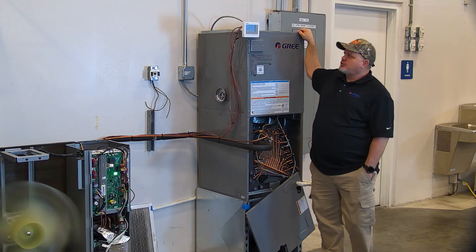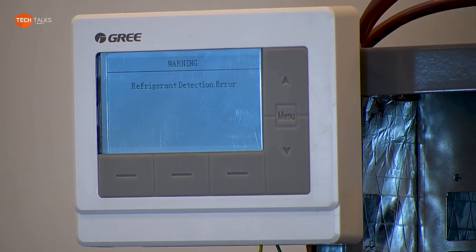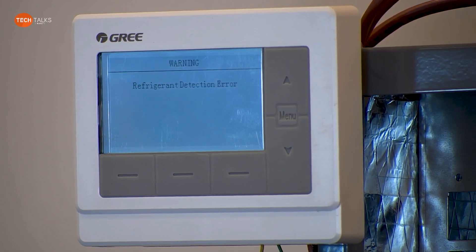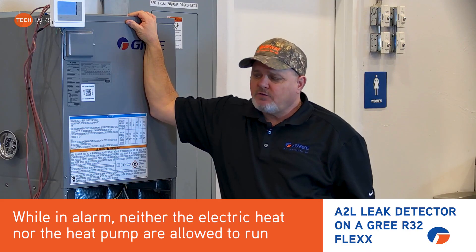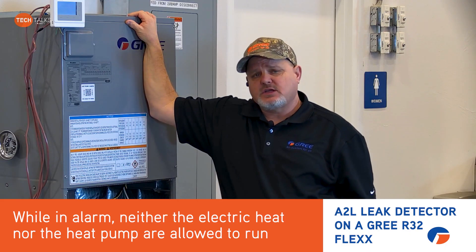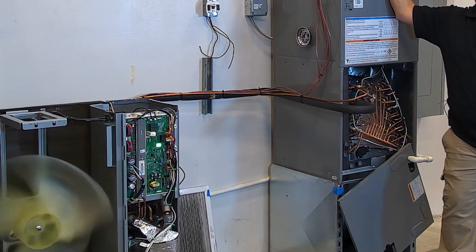On the wired controller, it will also show refrigerant detection error, meaning that it has reached the concentration level to actually set off the alarm. While in alarm, neither the electric heat nor the heat pump is allowed to run. So even though when it went into alarm you saw the outdoor fan was still running, I can assure you the compressor shut off immediately.